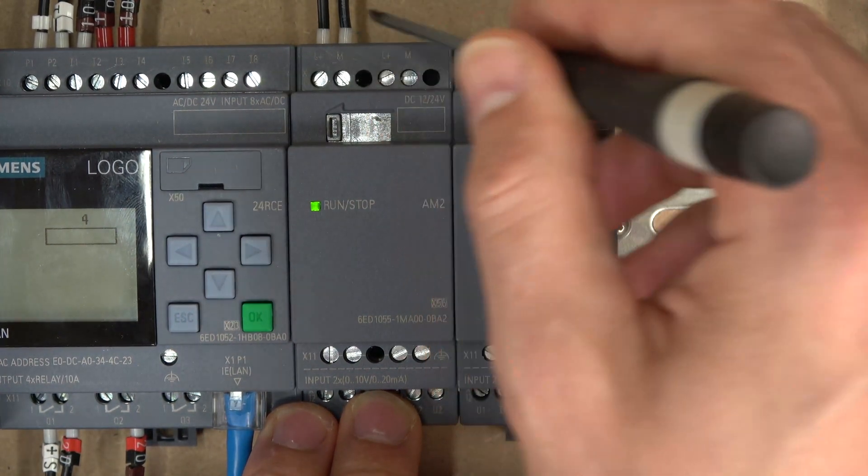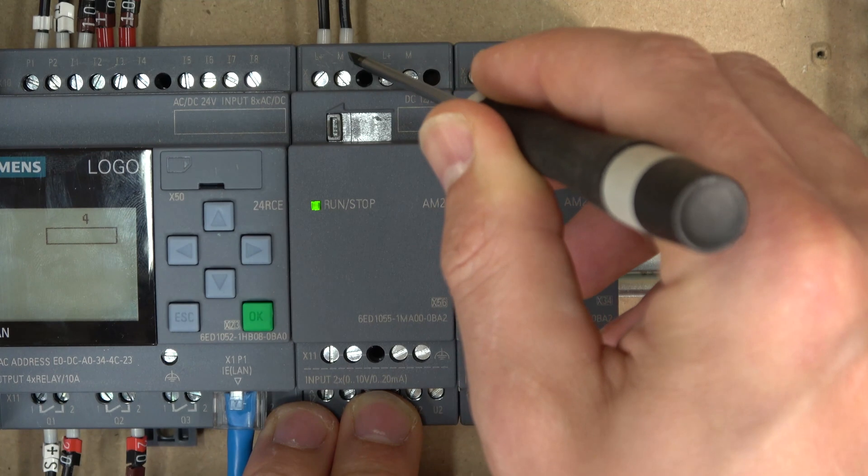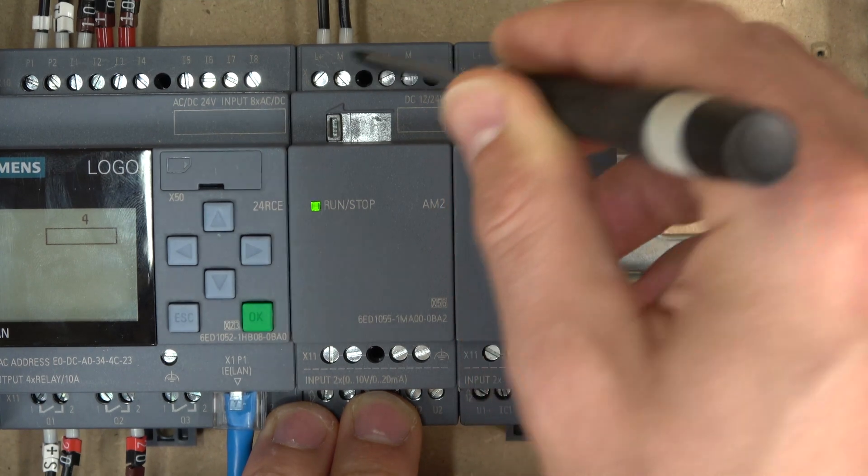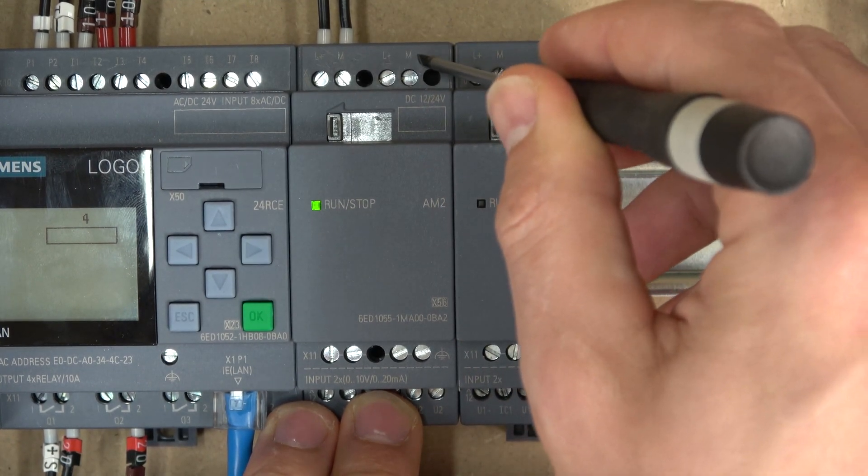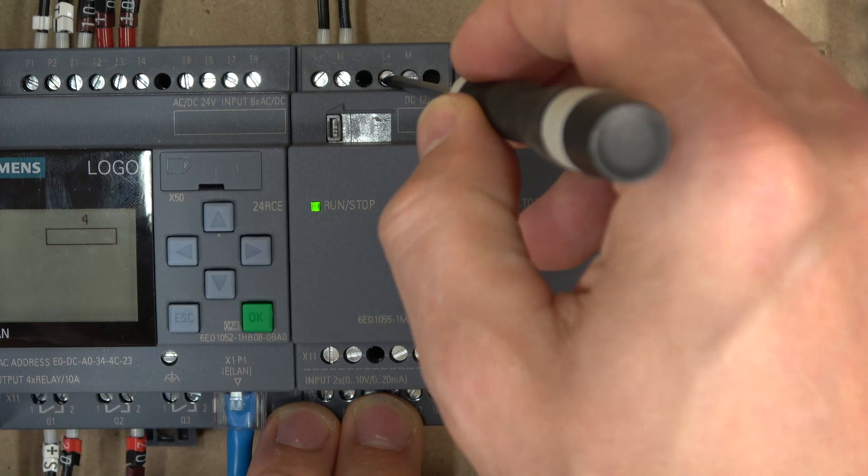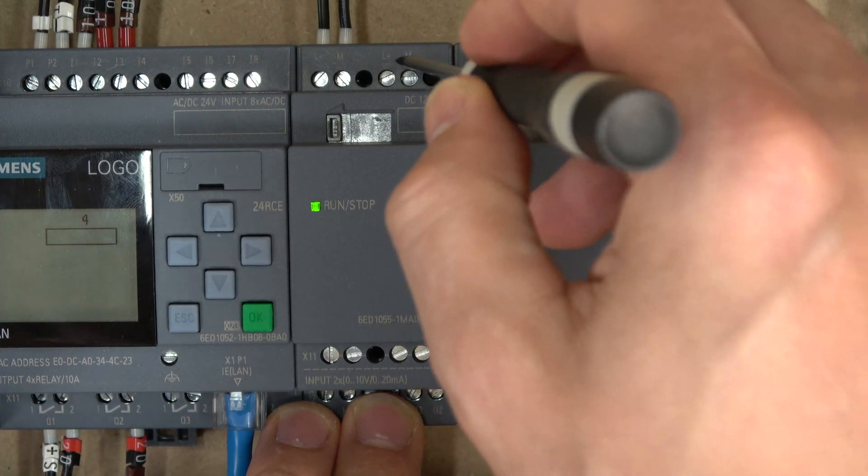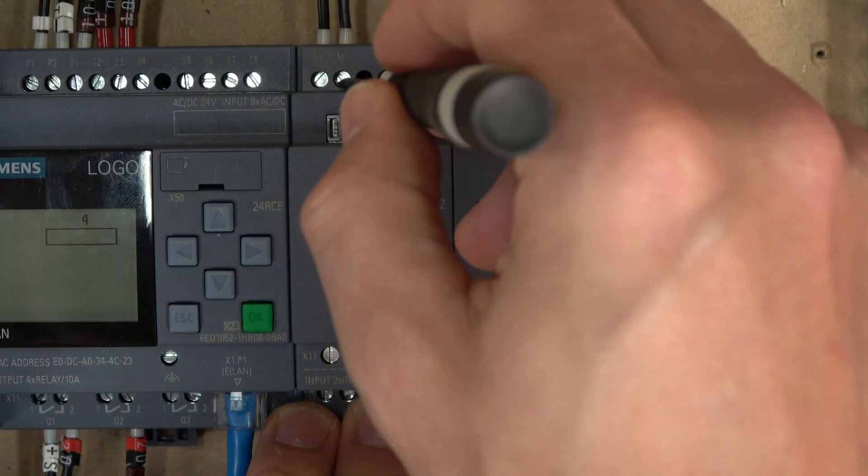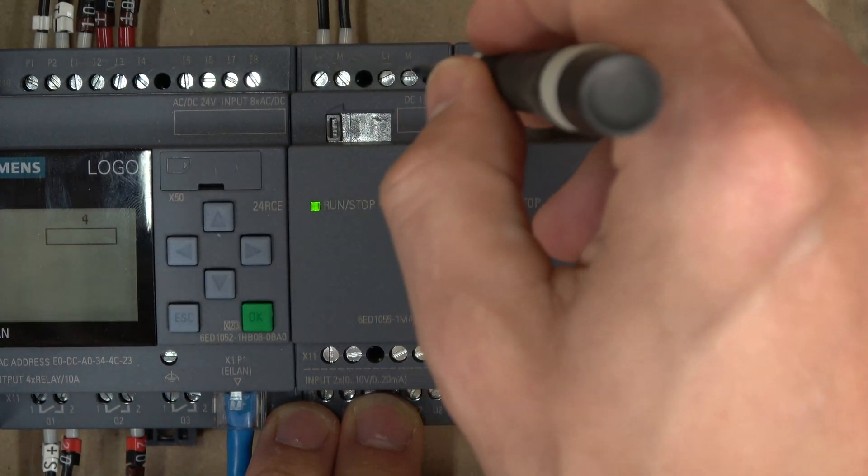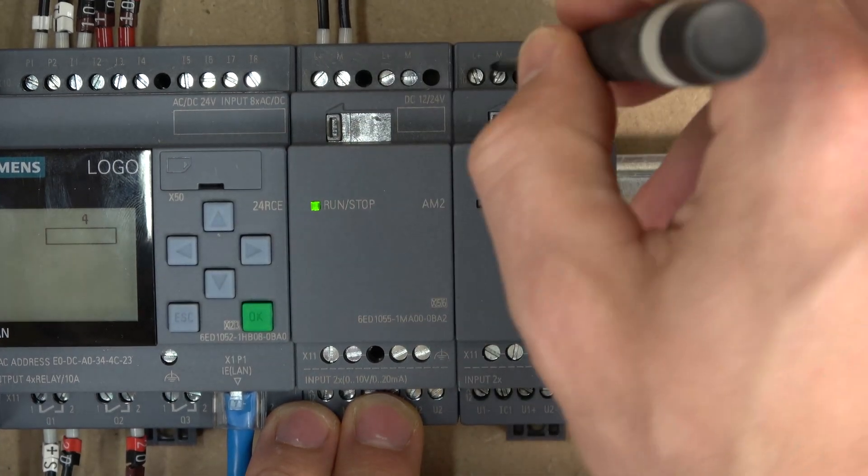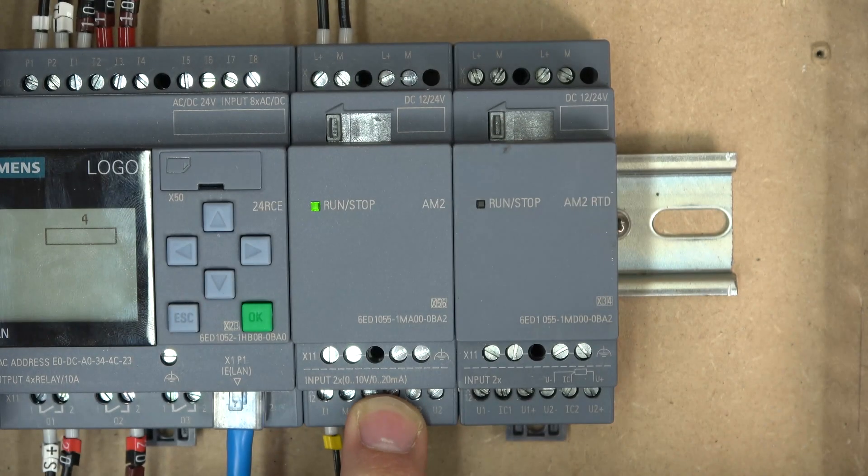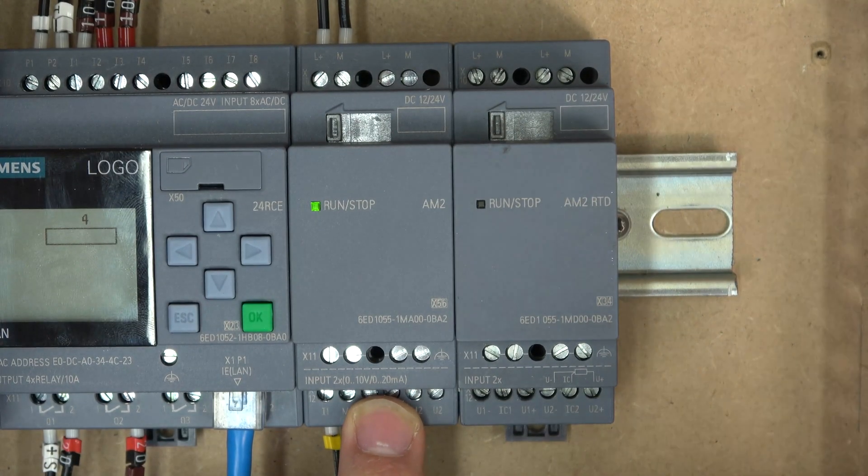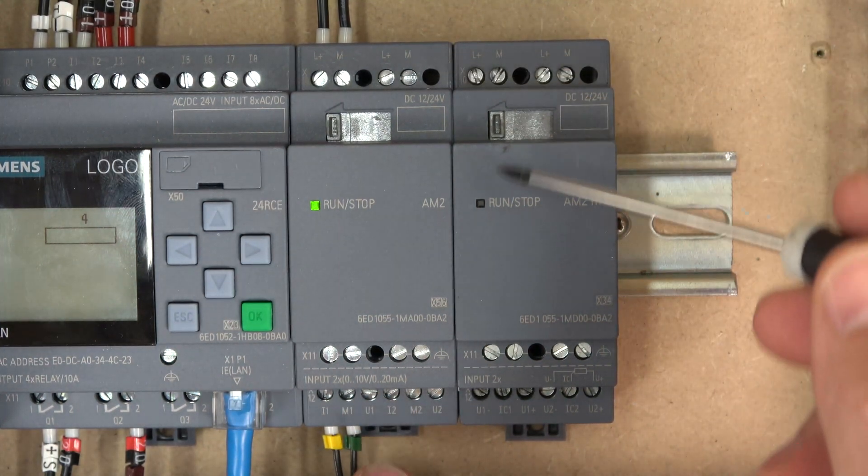This L plus and M, that's a 24 volt DC supply and this L plus and M here is an extra point Siemens added. As soon as you put power to these two, these two have it as well, so you can just spare off and go for your next card which is quite nice of them to do. It's pretty well done for that.